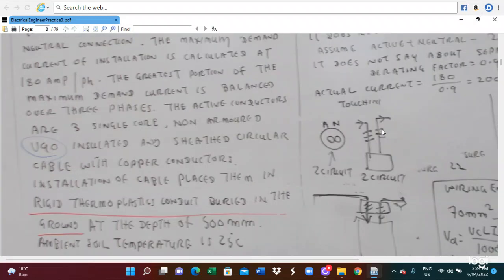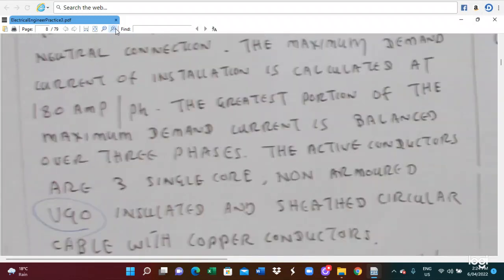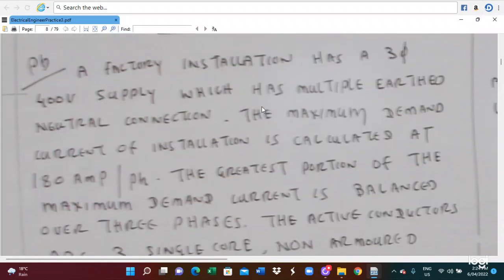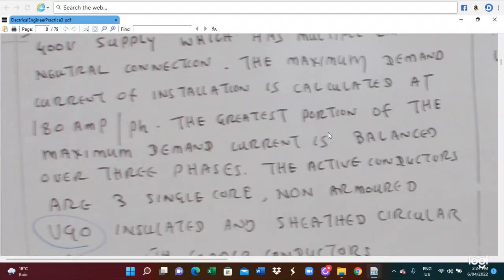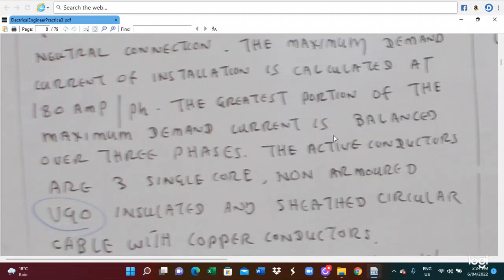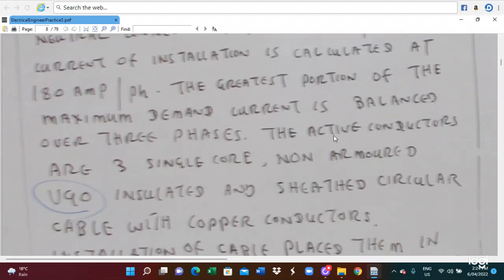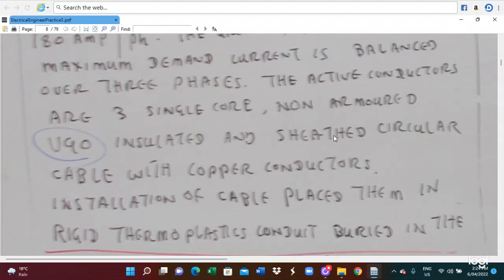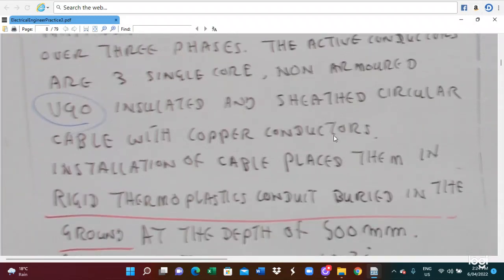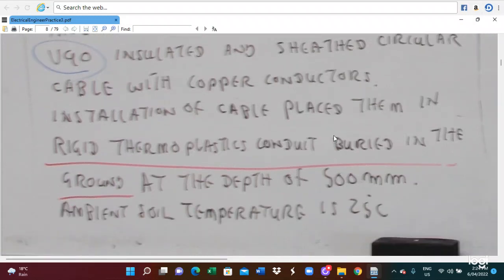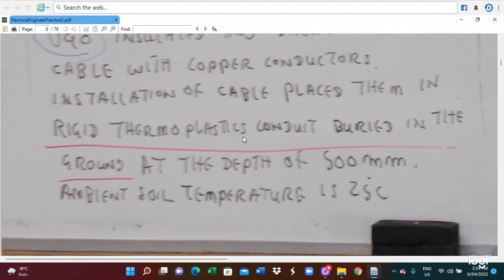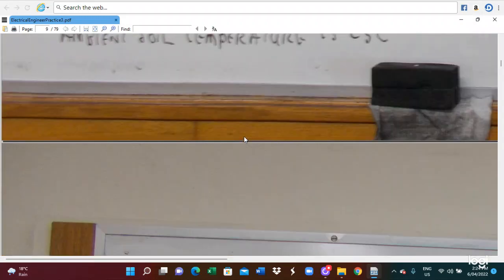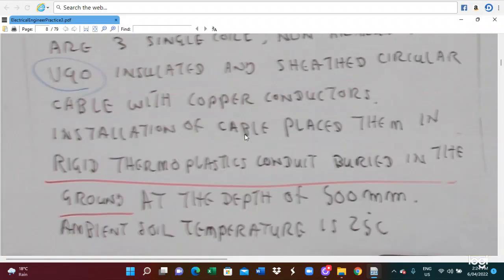Okay, this problem: a factory installation has a 3-phase 400 volt supply, with a multiple earthed neutral connection. The maximum demand current of the installation is calculated at 180 amperes per phase. The greater portion of the maximum demand current is balanced over the 3 phases. The active conductors are 3 single core non-armoured V90 insulated and sheathed circular cables with copper conductors. The cable is placed in rigid thermoplastic conduit buried in the ground at a depth of 500 millimeters, at an ambient soil temperature of 25 degrees centigrade. So this is what the problem gives.